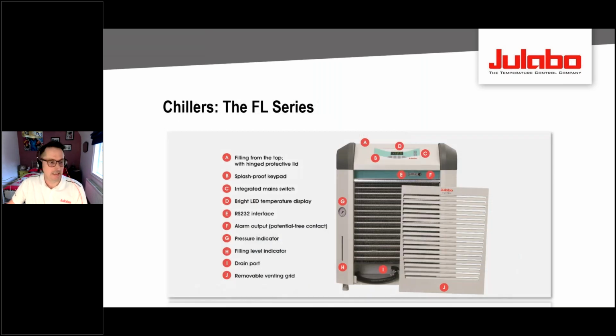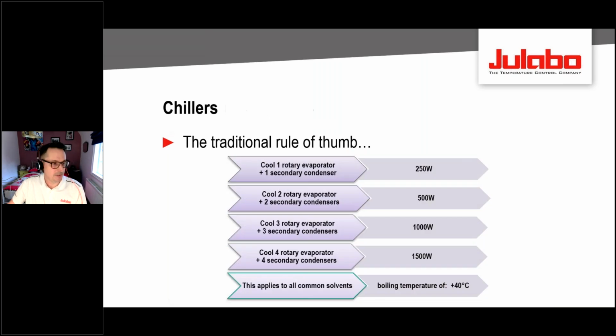A traditional rule of thumb on rotary evaporators, talking about 3 liters and below, is that each one typically needs somewhere in the region of 250 to 300 watts of cooling. If your calculations give numbers that vary dramatically from that, check your data.